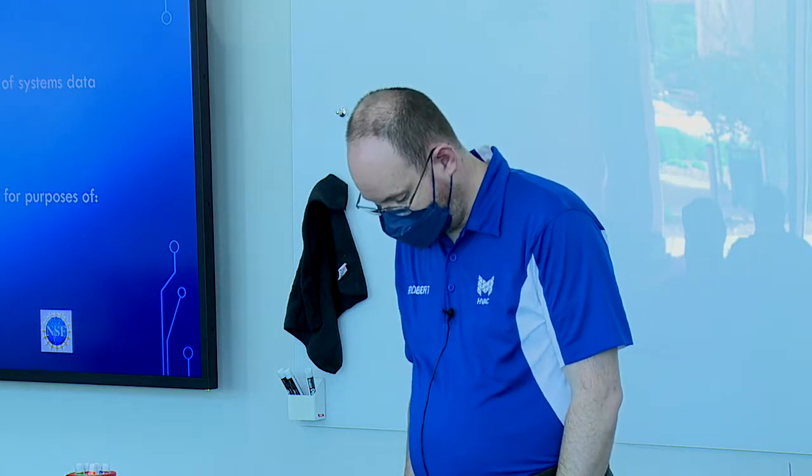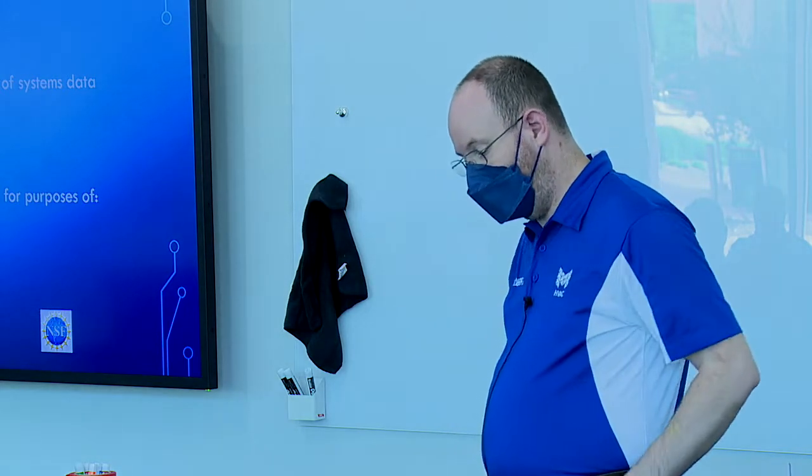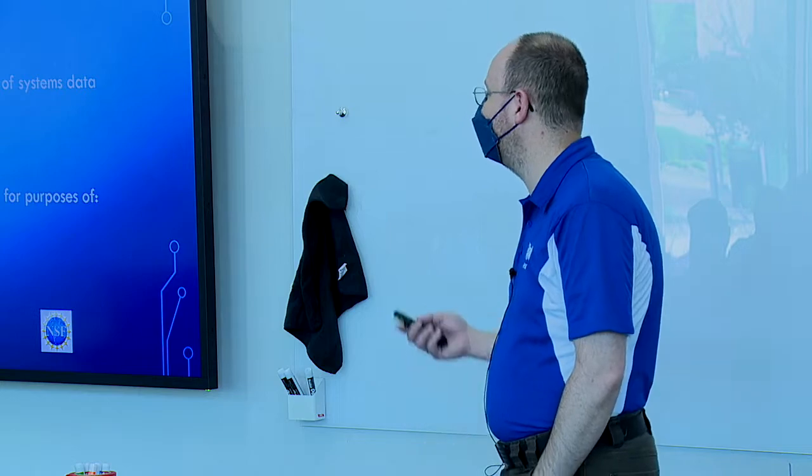One of the biggest nuisances is if you have a chiller go down and it's the only chiller in the building, and you have all of a sudden 800 zones go out of temperature range, and you get 800 alarms. This thermostat, this zone is out of range, this zone is out of range. How cool is that? You're absolutely right. Change the automation. I like that.